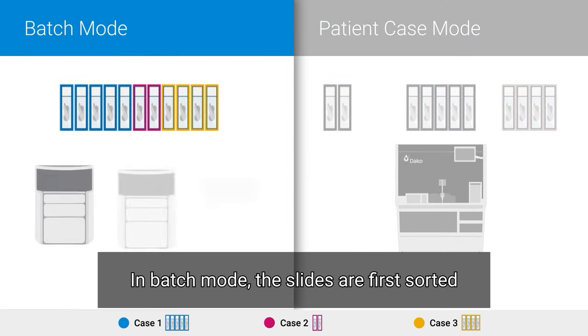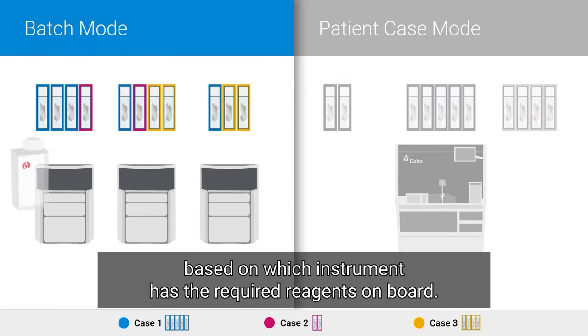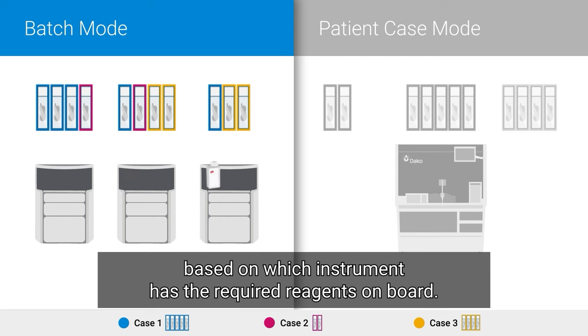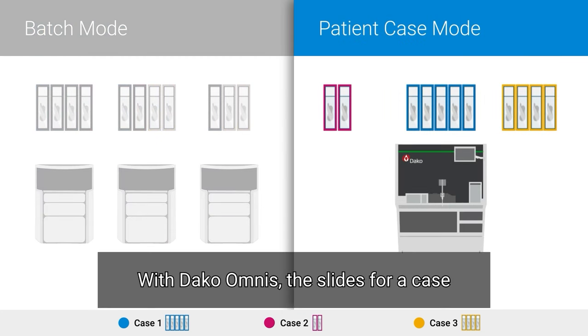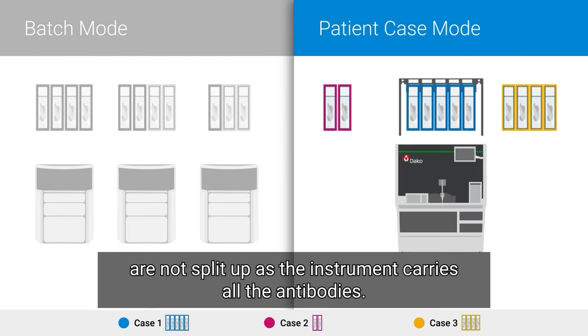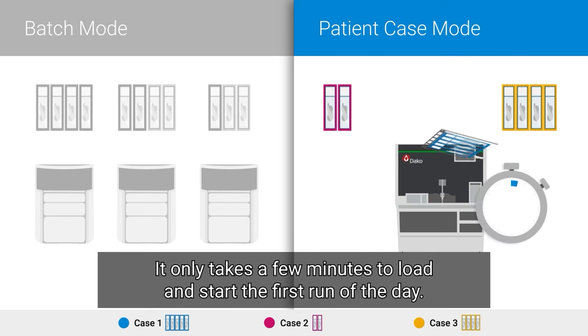In batch mode, the slides are first sorted based on which instrument has the required reagents on board. With Dako Omnis, the slides for a case are not split up as the instrument carries all the antibodies. It only takes a few minutes to load and start the first run of the day.